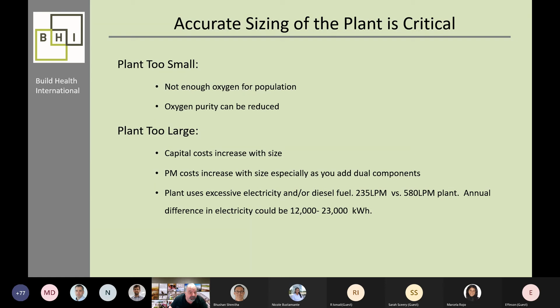I just gave an example of a 235 liter per minute plant versus a 580 liter per minute plant. That difference in electricity could be 12 to 23,000 kilowatt hours per year. And we typically figure if you're providing electricity through a diesel generator, which is often the case in low resource settings, you could be paying 50 to 65 cents US per kilowatt hour. So this could be $10,000 or $15,000 in cost. Next slide, please.